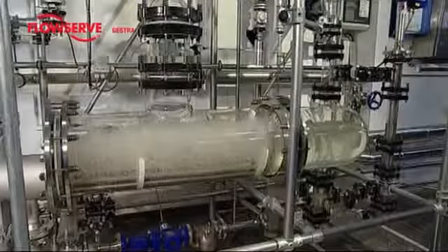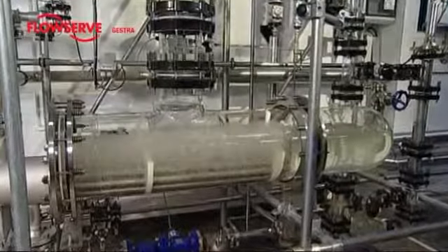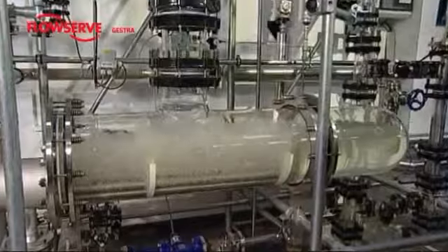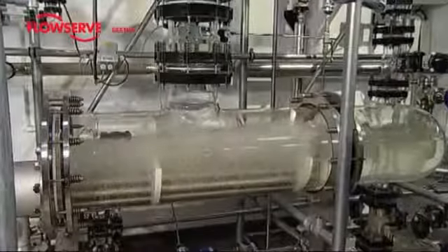Here it's necessary to use a 3-component control system to consider the steam outlet, the feed water supply, and the water level in the steam boiler, and therefore prevent premature throttling of the feed water control valve.